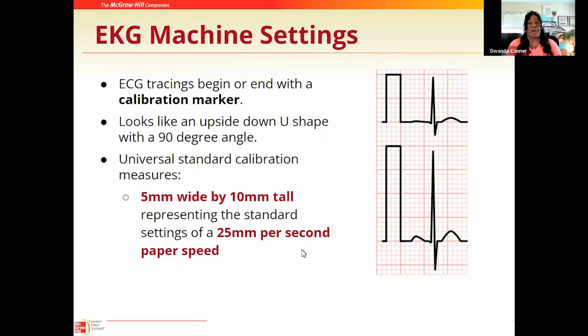Also on your EKG paper, as your results start to print, you're going to see what's called a calibration marker. The calibration marker will begin or end your EKG rhythm. It does look like an upside down U, and it has a 90-degree angle. Now there are what's called universal standard calibration measures, in which we really don't alter any of the settings on the EKG, but we would want to verify that we're falling within these parameters for an accurate reading.